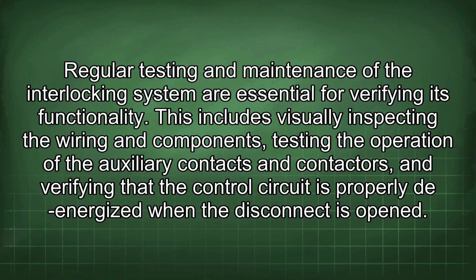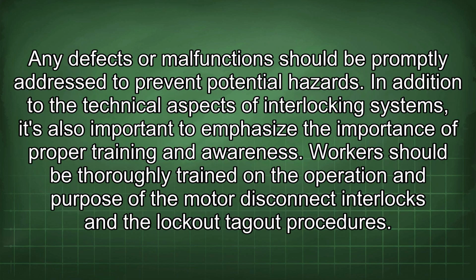Regular testing and maintenance of the interlocking system are essential for verifying its functionality. This includes visually inspecting the wiring and components, testing the operation of the auxiliary contacts and contactors, and verifying that the control circuit is properly de-energized when the disconnect is opened. Any defects or malfunctions should be promptly addressed to prevent potential hazards.